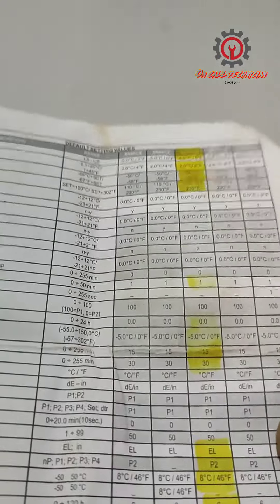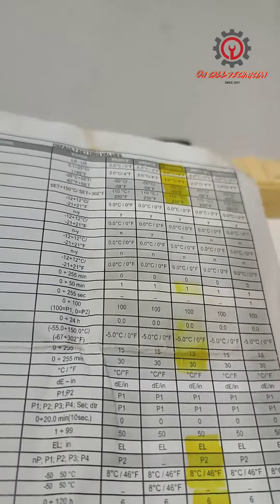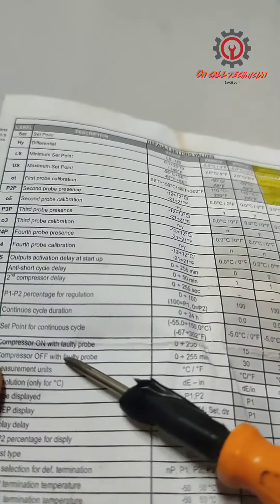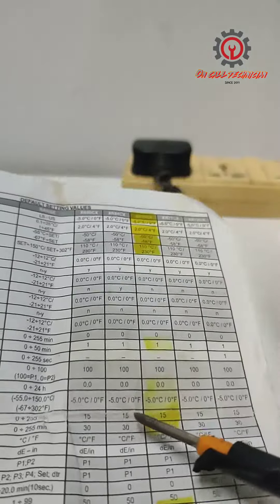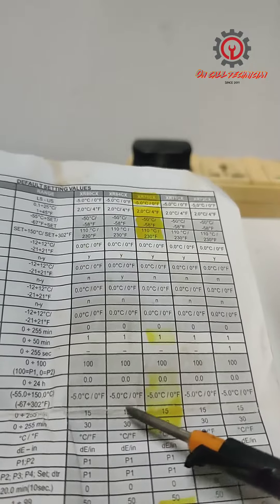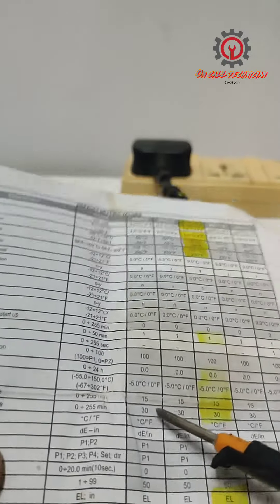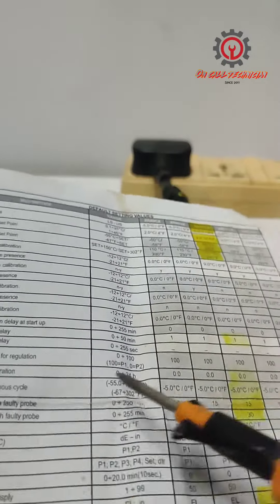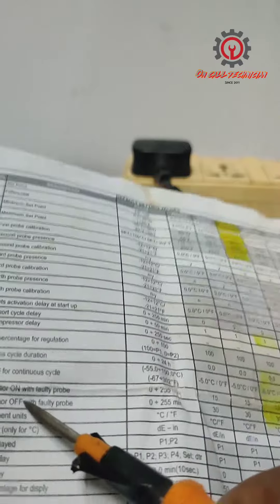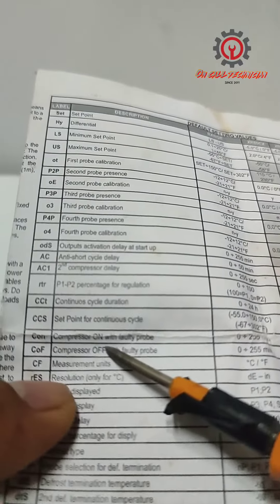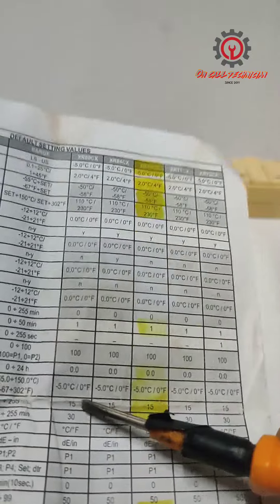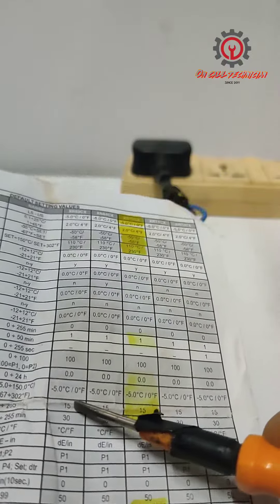C on, compressor on with faulty probe - usually the default here is 15, and 30 for the compressor off. They put a default here, meaning the unit runs for 15 minutes.